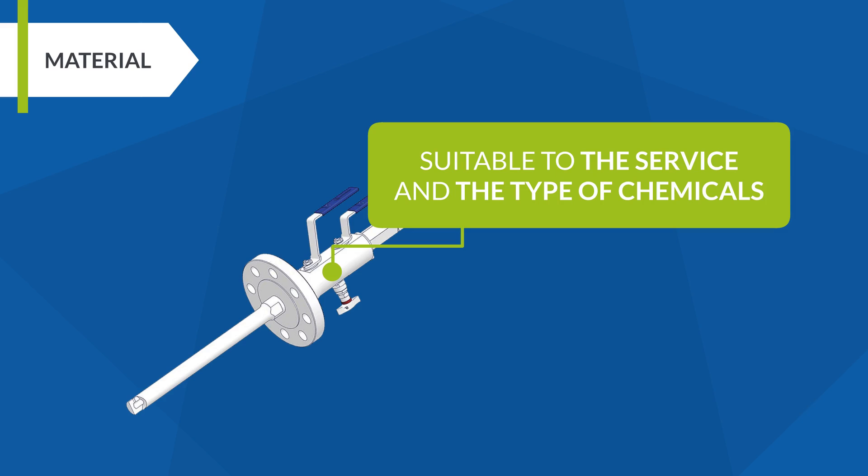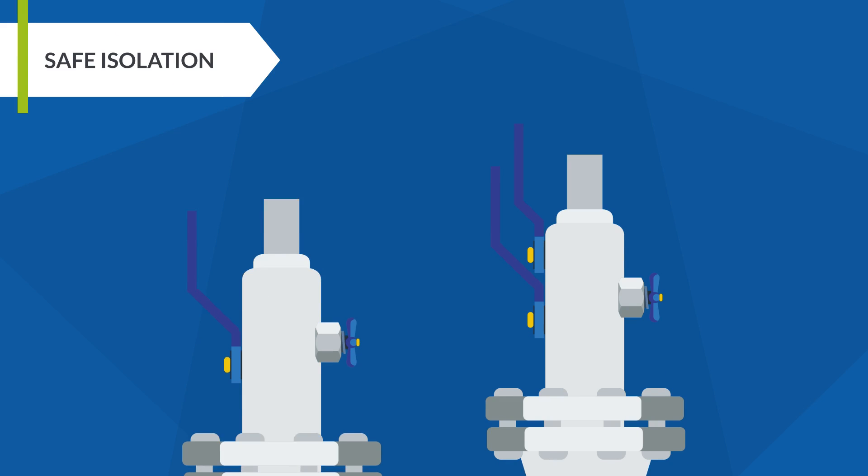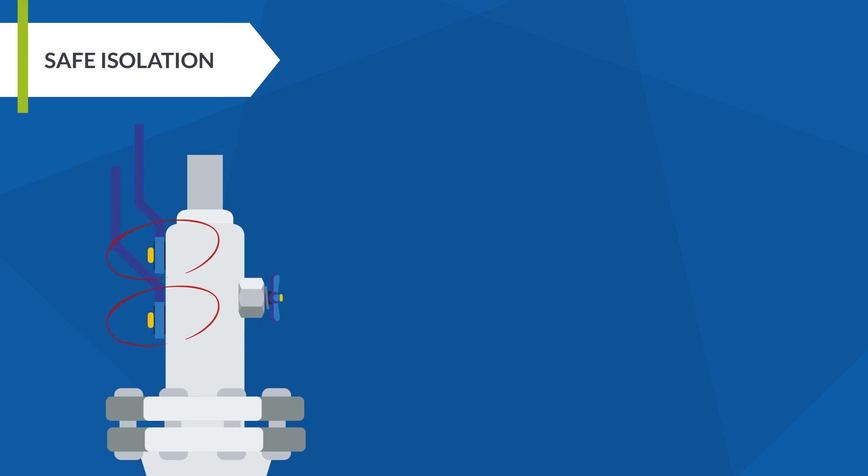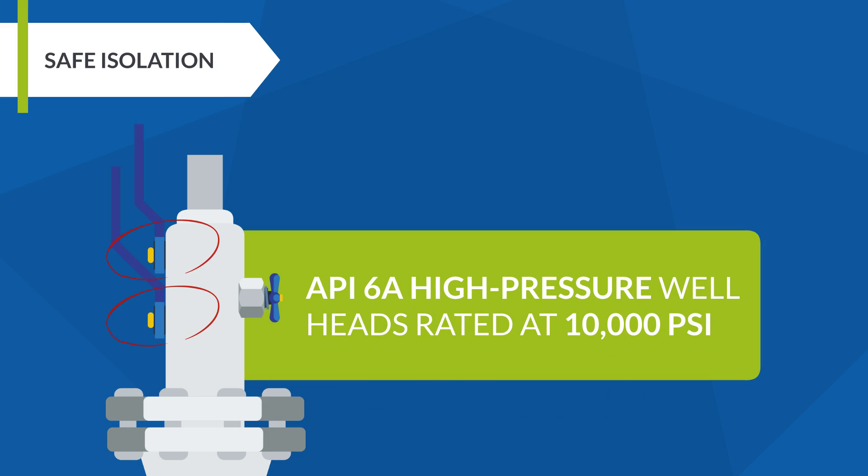Safe isolation. There are quill designs without integral isolation valve or involving only single isolation. To upgrade the safety level, an integral DBB valve is important in certain applications and media. This is the case with injection quills installed in API 6A high pressure wellheads rated at 10,000 psi.